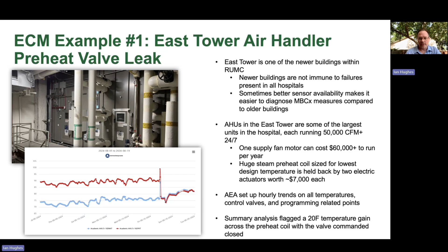We did a little bit of math and we figured out that one supply fan motor could cost about 60 grand to run per year. We've got huge steam preheat coil size for lowest design temperature. These things are very expensive, but what we did with our partners at American Energy Assets is set up hourly trends, looking at temperature control valves and programming, and they flagged a 20-degree temperature difference across a preheat coil and valve that were programmed to be closed, which was kind of interesting. So they went out in the field and sure enough found these things were red hot. They took the thermal imager and saw that they were stuck wide open. And as those valves were stuck wide open, we were wasting massive amounts of energy in the dead of summer, heating air and then cooling it off for the building so that they were comfortable.